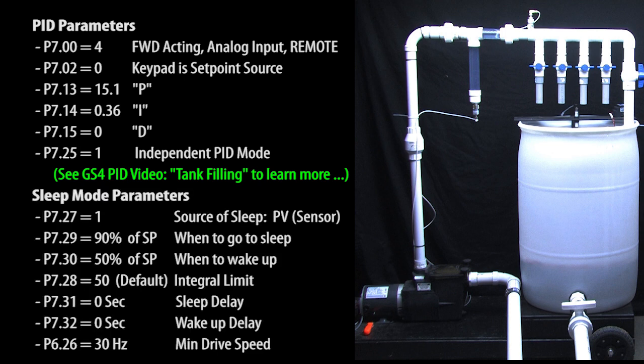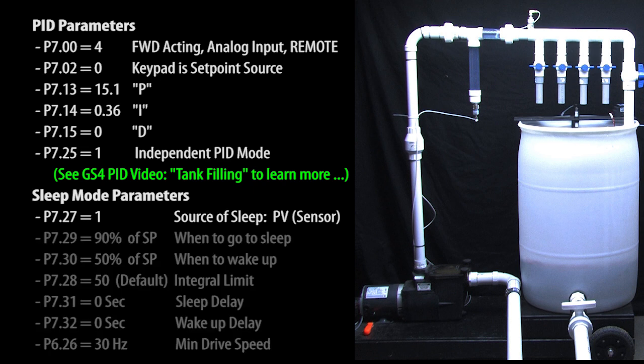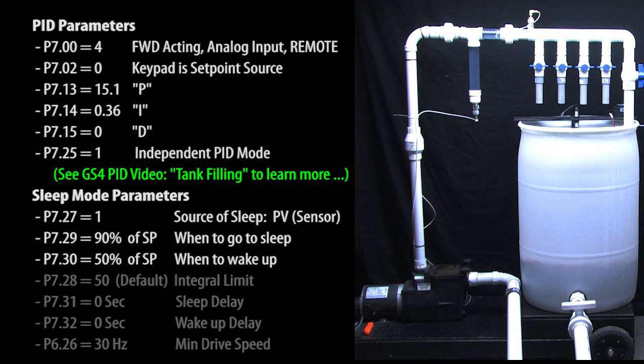So now we just set the sleep mode parameters. First we need to tell sleep mode to use the process variable or sensor feedback to make its decisions. Now this is important to understand. In sleep mode 3, the sleep and wake levels are not absolute. They are a percentage of the set point.